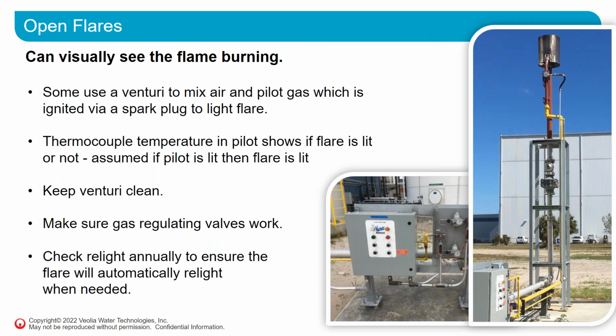Then going back to the open flares, they're open, you can visually see the flame burning. Some use a venturi to mix air in the pilot gas, which is ignited by a spark plug in order to light them. There is a thermocouple in the pilot, and you can use that thermocouple temperature to tell you whether or not your flare is lit. It is assumed if your pilot is lit, then your flare is lit.